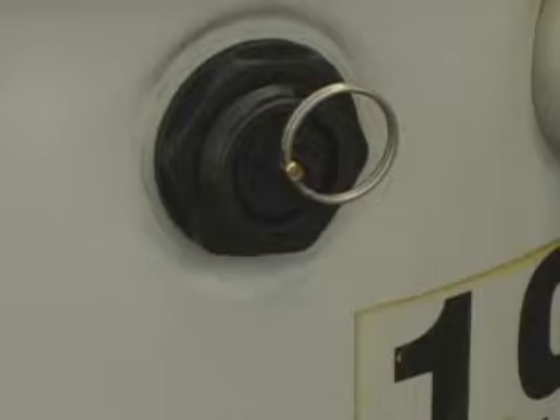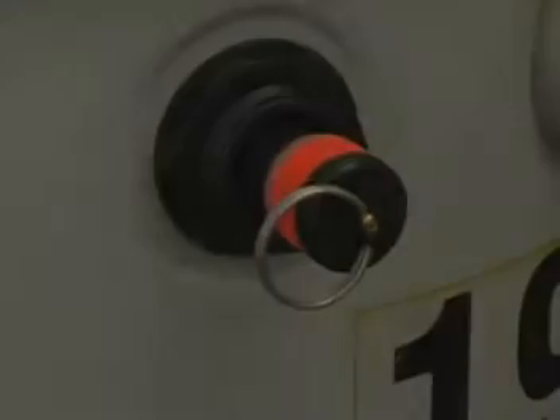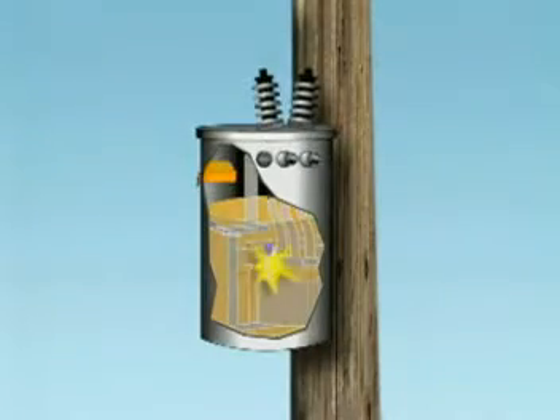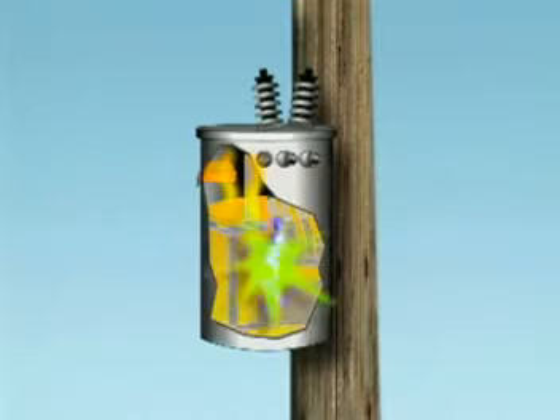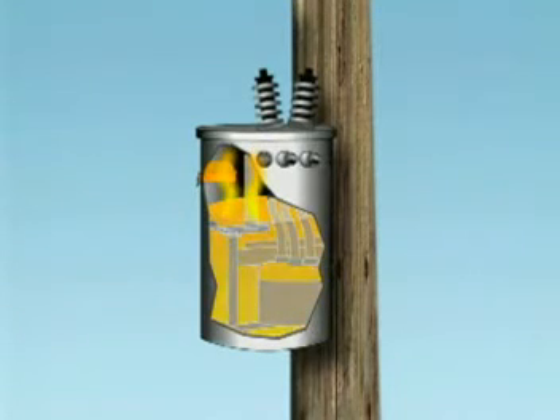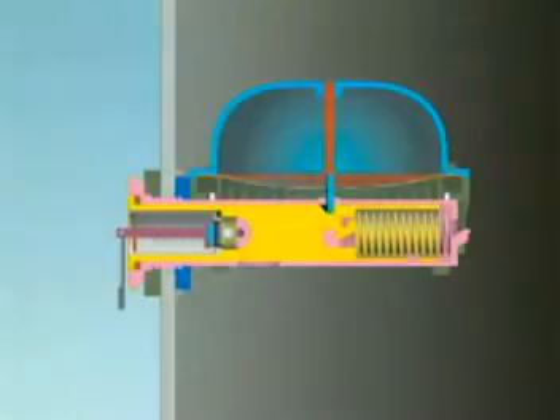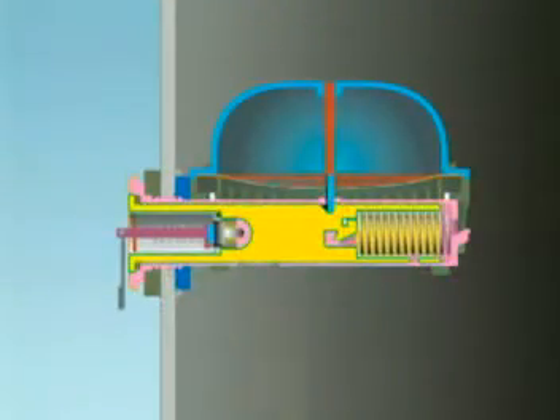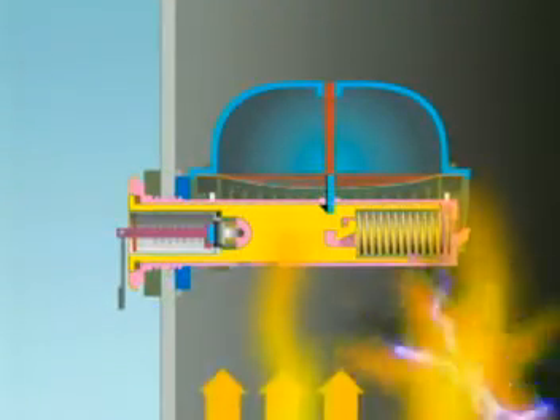Now, let's look at how the device works as a fault detector. When a fault occurs, there's a sudden increase in tank pressure, and gases collect in and above the oil. The fault produces several types of gases. When these gases mix in particular proportions, they become explosive. In this graphic, the IFD is in the normal position.